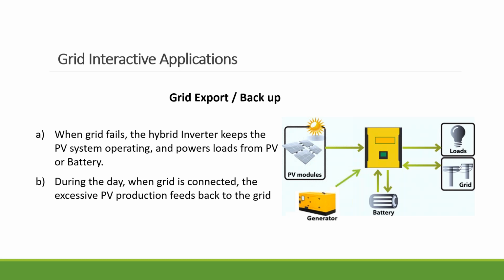In grid interactive applications, backup is still the number one application. If you look at the graphic here, what's different from off-grid is that now you do have a grid. As you can see, the inverter can take the power from the PV and feed it back to the grid during the day when there's excess power. And when the grid goes off, it will form its own island system, so you have the PV or the battery powering the load. Sometimes people will also add a generator as a third energy source.